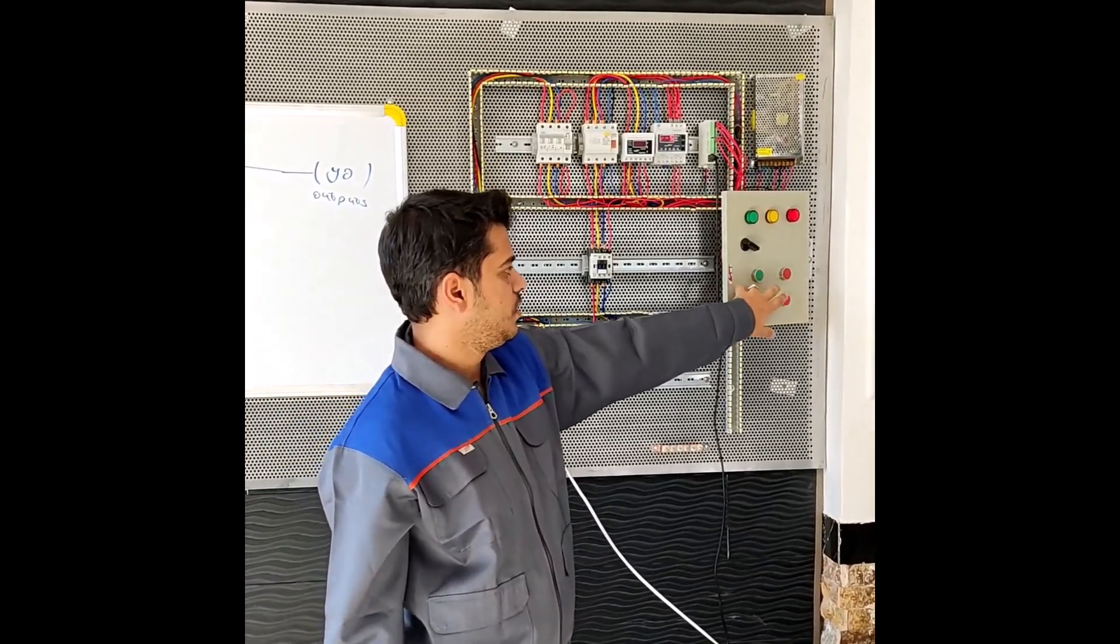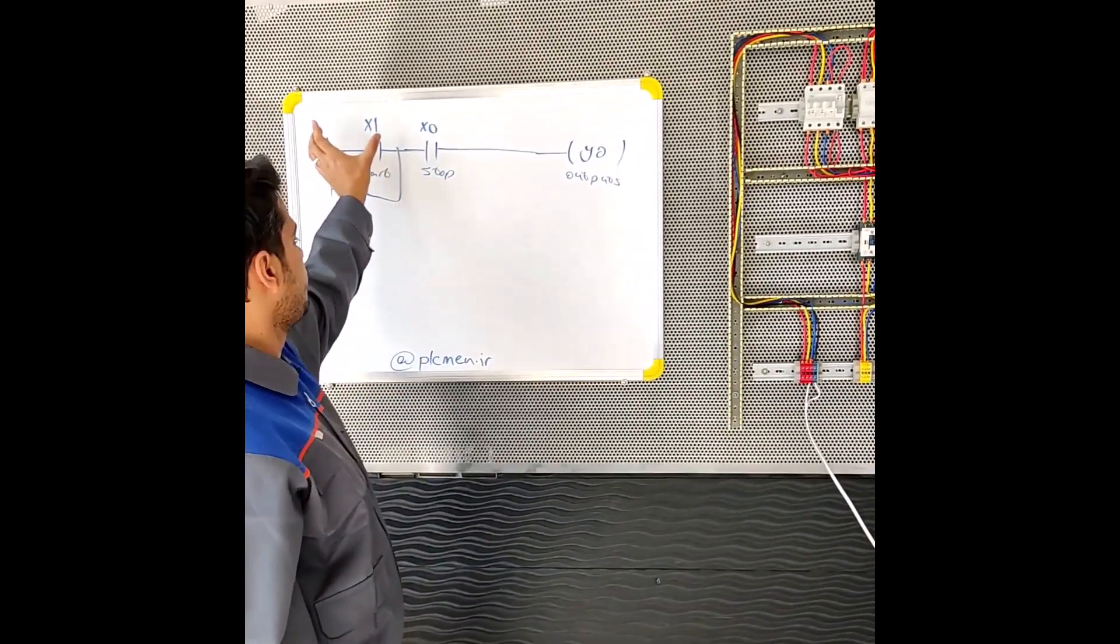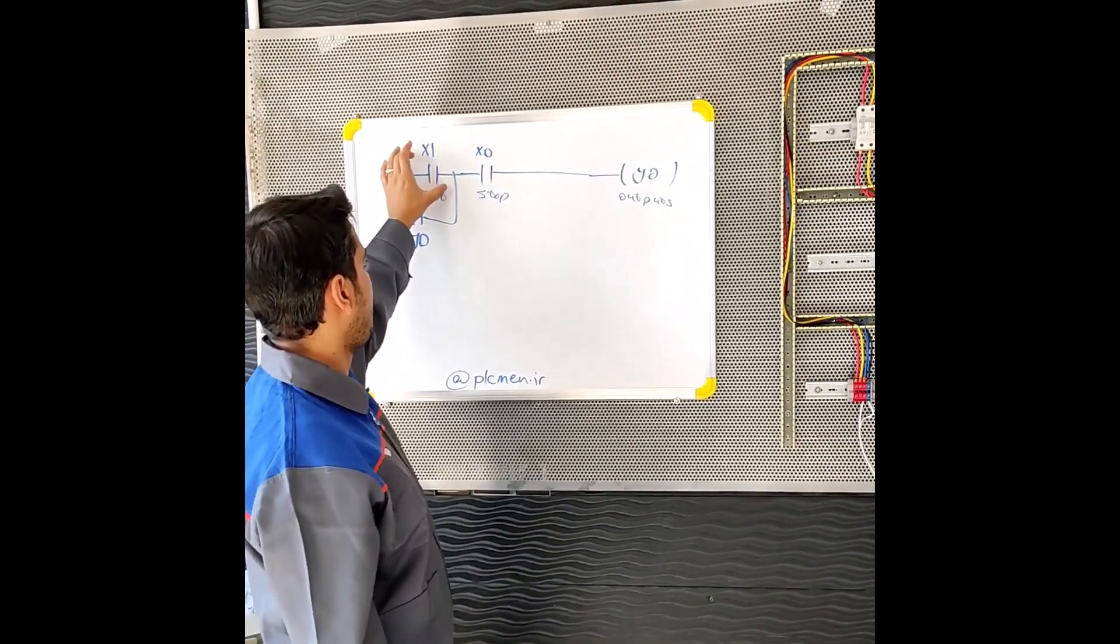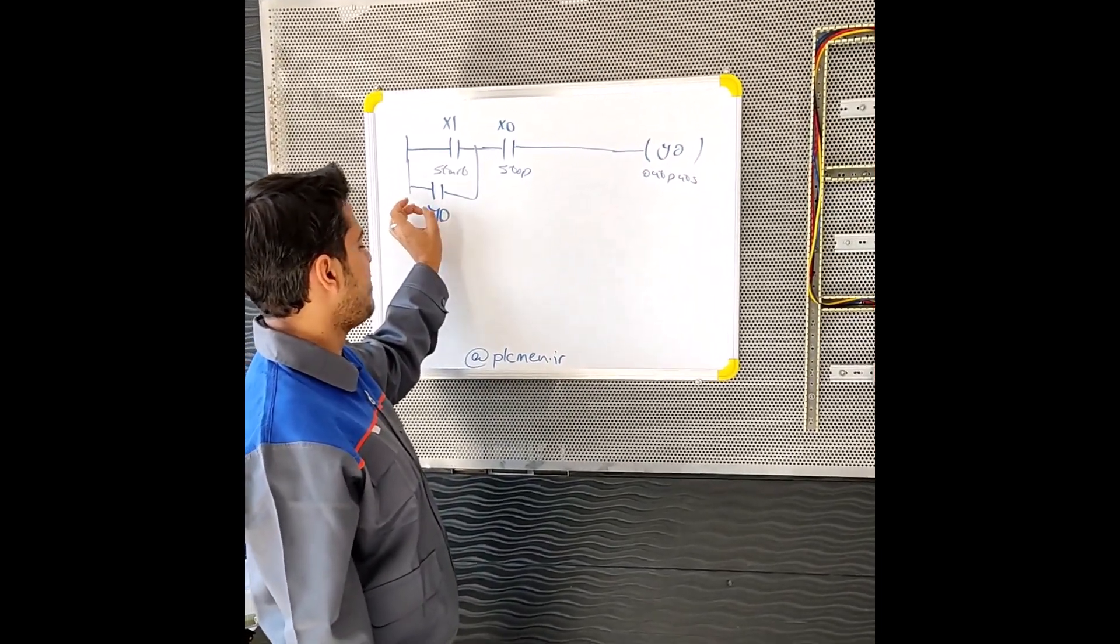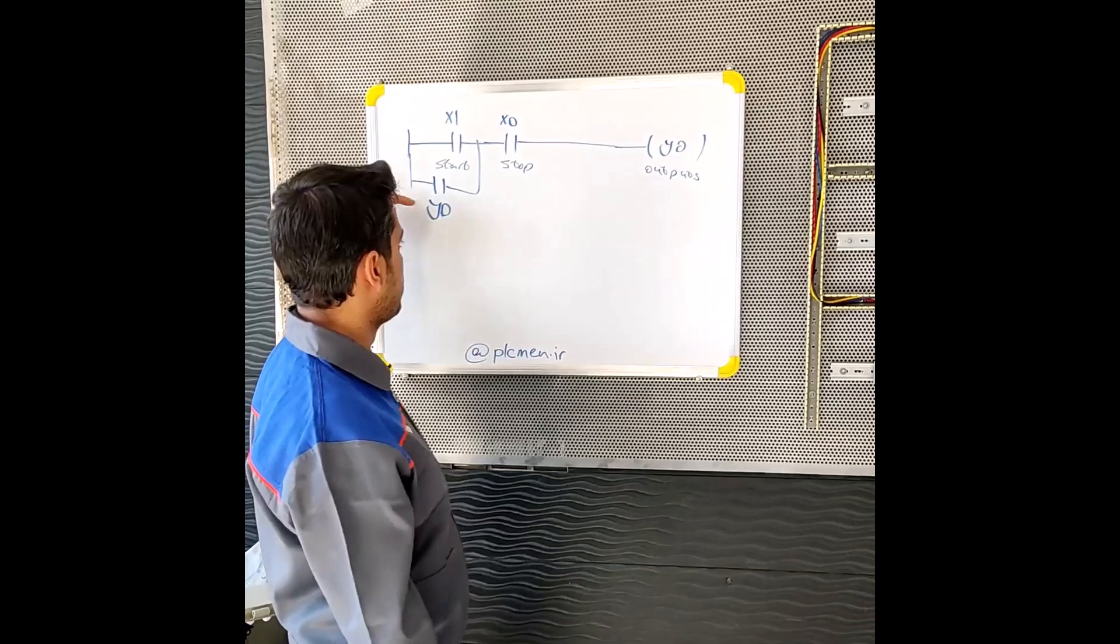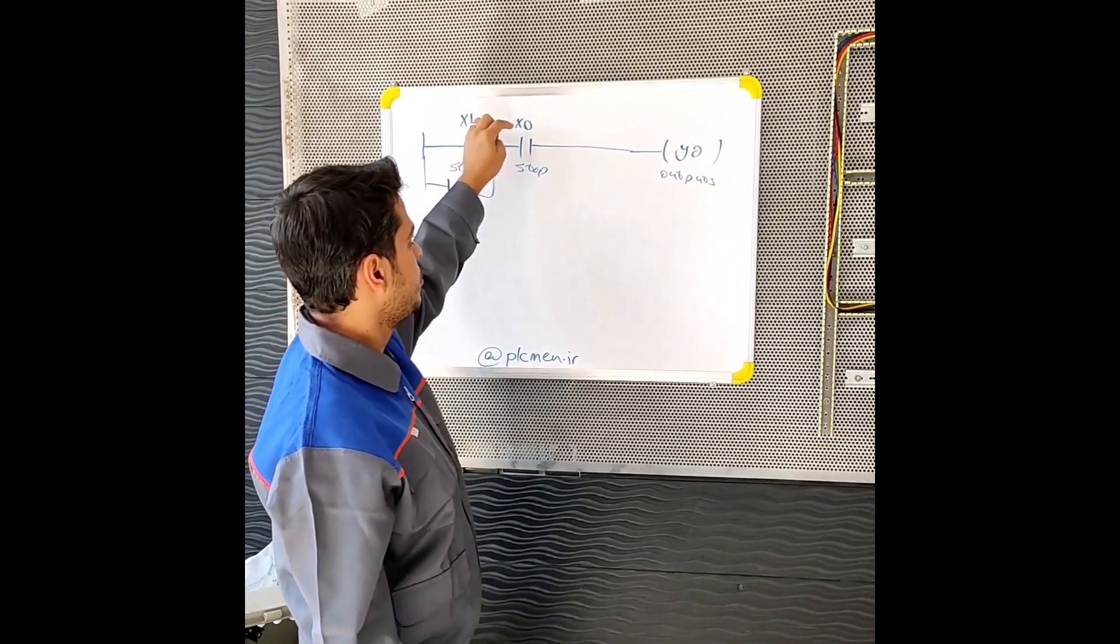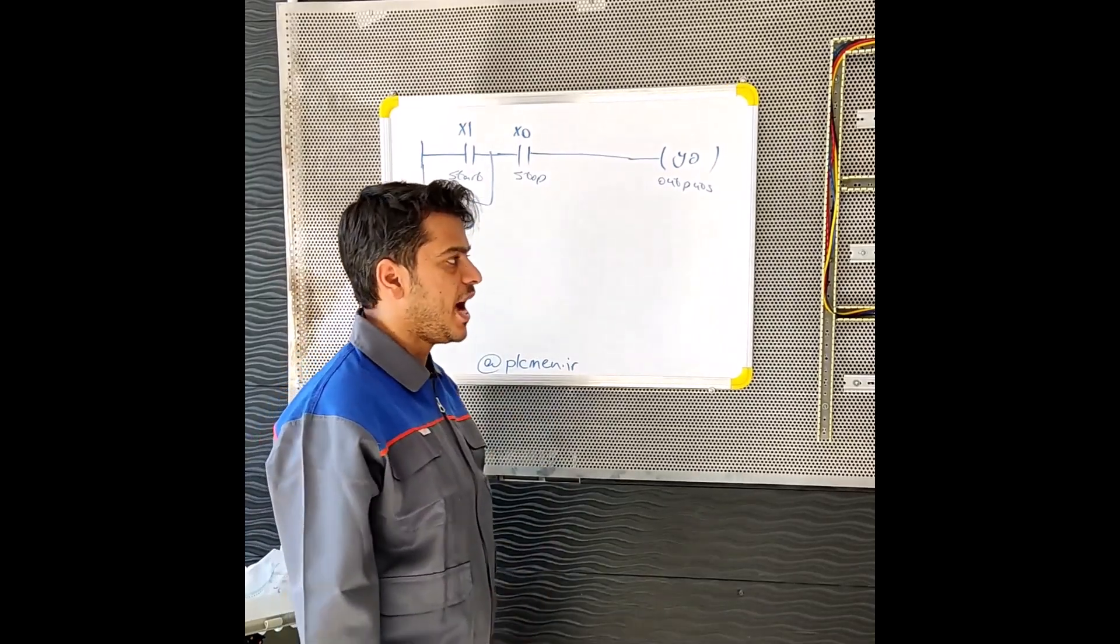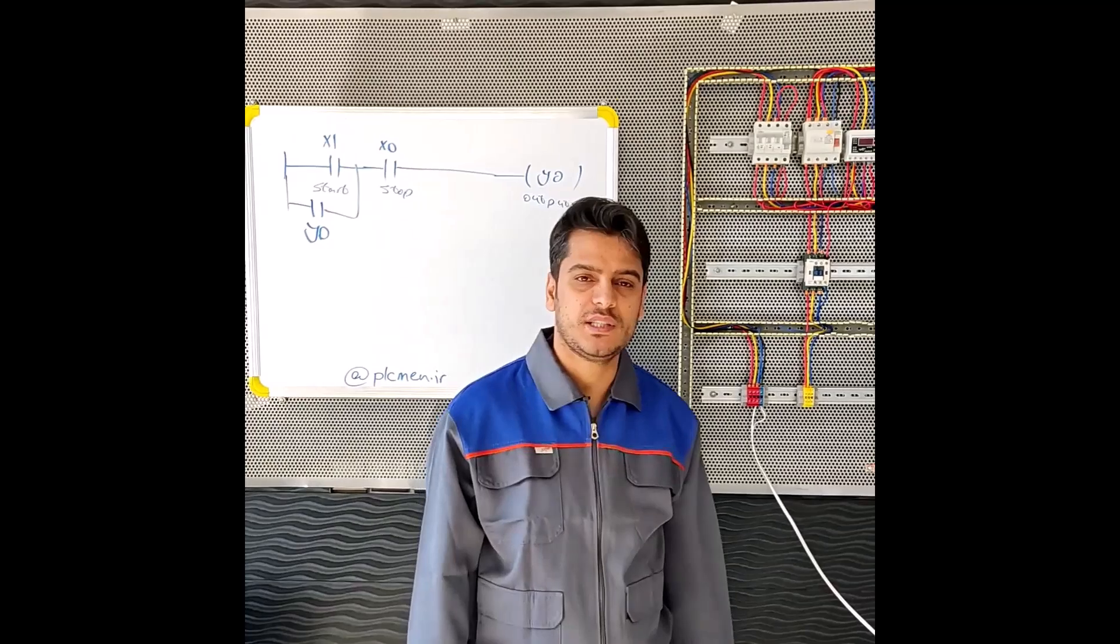Because we parallel the output with the input, when the start is activated, the output is activated and this contact is activated. It gives the electric current that passes through the power unless we cut off this power by using the stop input.